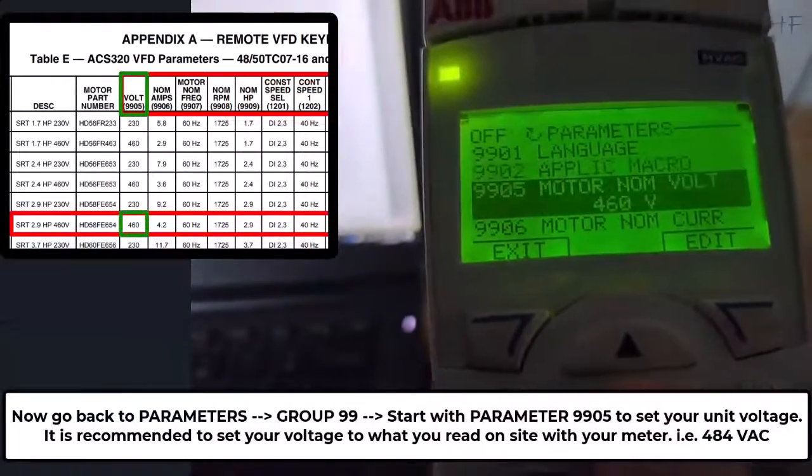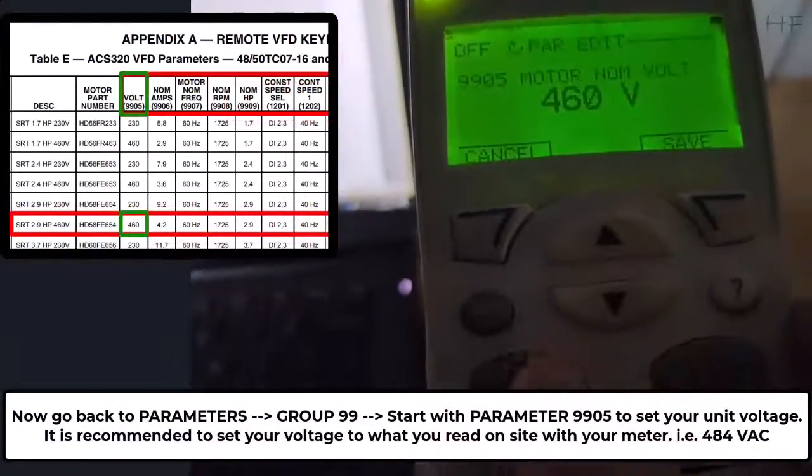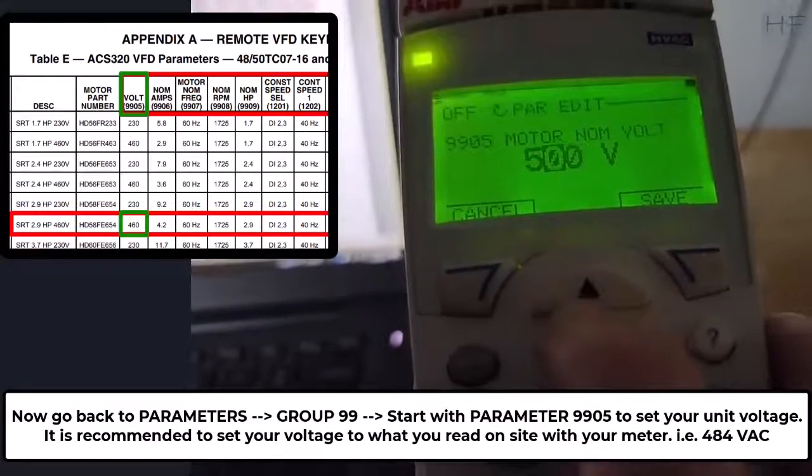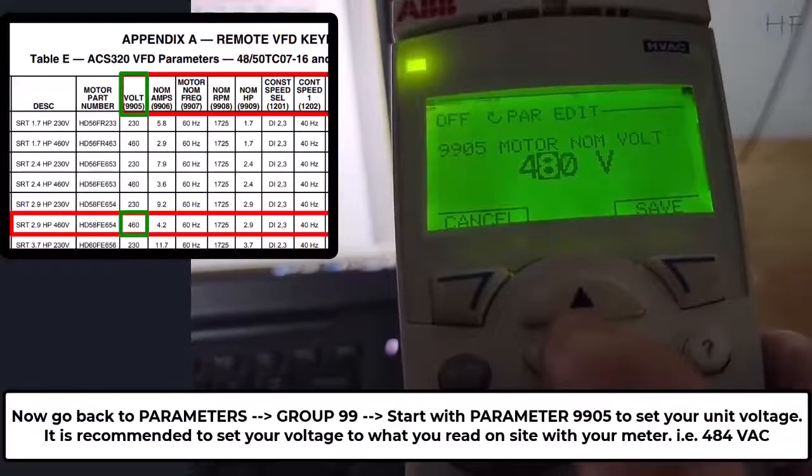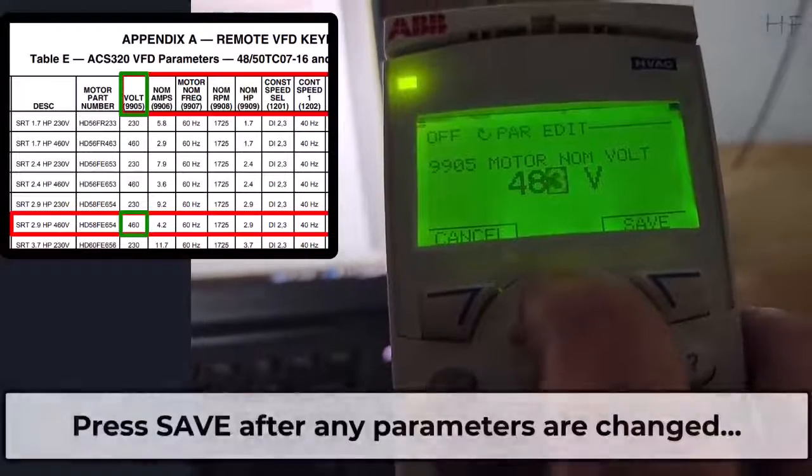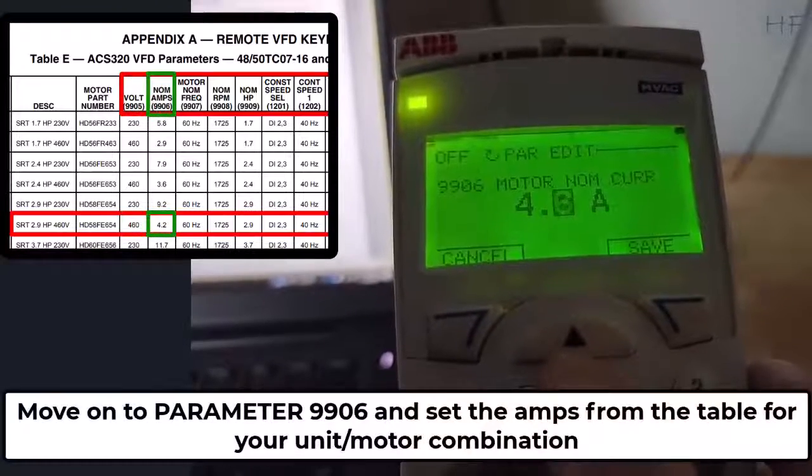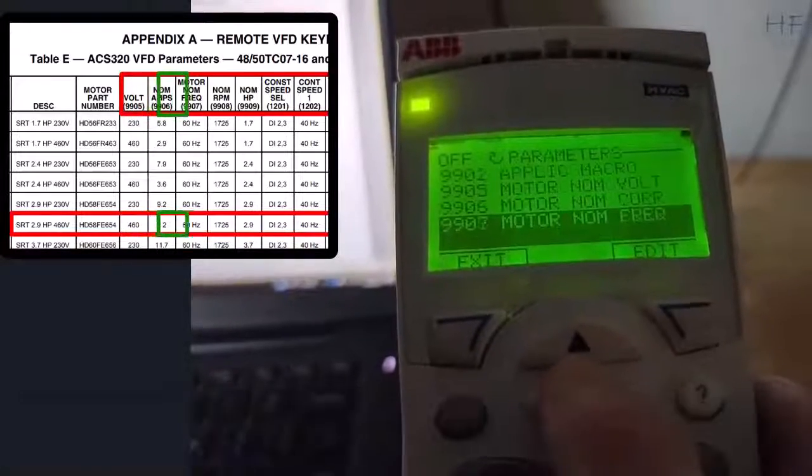Now go back to parameters, enter group 99 to find parameter 9905 and set your unit voltage. It is recommended to set your voltage to what you read on site with your meter. After changing any parameter, make sure to press save. Move on to parameter 9906 and set the value from the table for your specific unit.